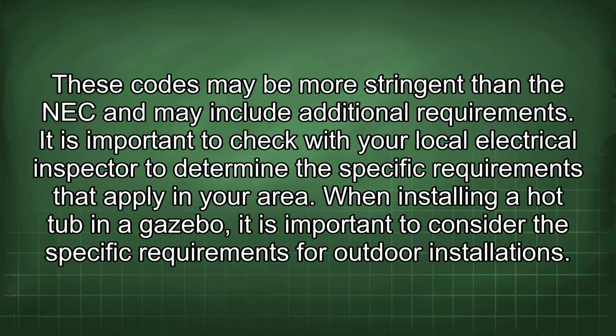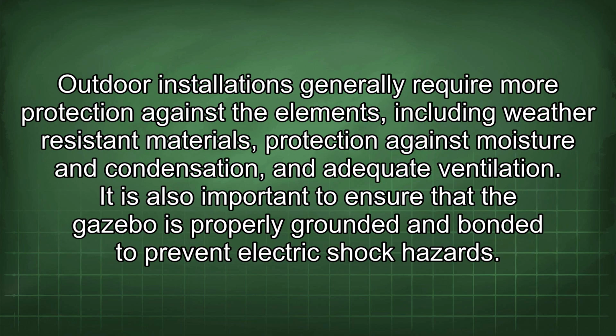These codes may be more stringent than the NEC and may include additional requirements. It is important to check with your local electrical inspector to determine the specific requirements that apply in your area. When installing a hot tub in a gazebo, it is important to consider the specific requirements for outdoor installations. Outdoor installations generally require more protection against the elements, including weather-resistant materials, protection against moisture and condensation, and adequate ventilation. It is also important to ensure that the gazebo is properly grounded and bonded to prevent electric shock hazards.